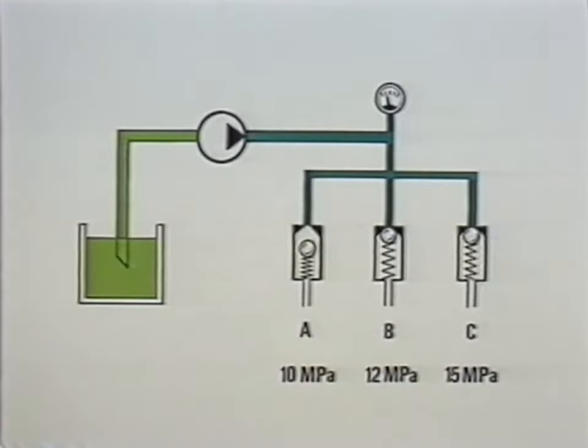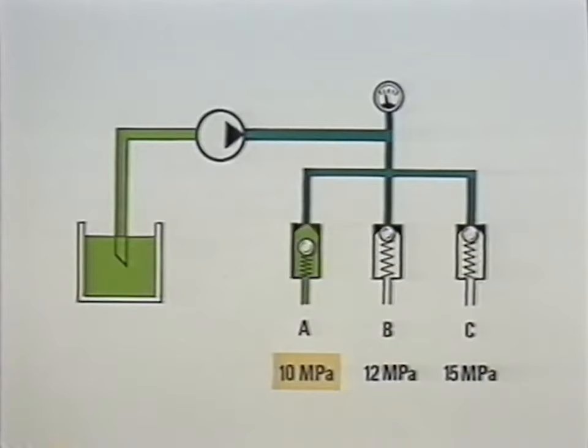When several pressure-limiting valves are connected in parallel, in other words, next to each other, the valve which has the lowest pressure setting will determine the system pressure.